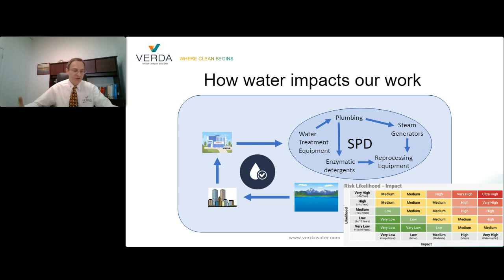The steam in your sterilizers is also impacted by the quality of the water feeding them. And while the facility maintenance departments can be very sophisticated in the methods they use to treat the steam feed water and install things like steam filters to remove contaminants and excessive moisture, that balance can be very delicate. And like the city in Flint, there may be limitations on just how much water quality can vary before it starts to impact the performance of the steam sterilizers, and issues like wet packs become more common.